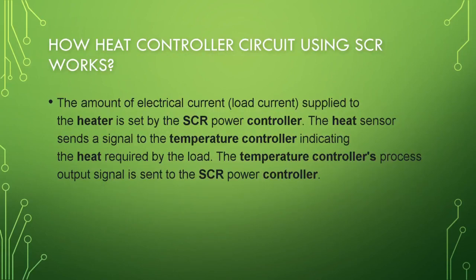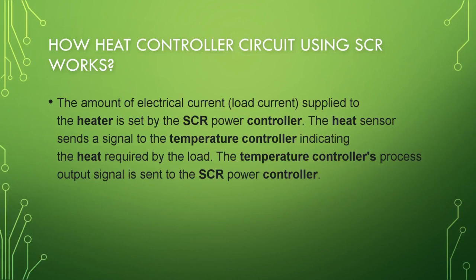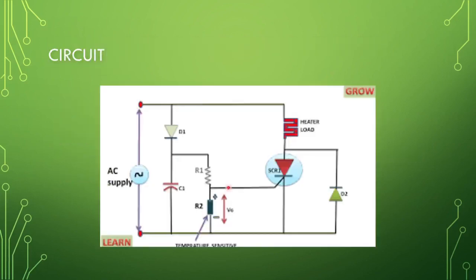Now, how does a heat controller circuit using SCR actually work? The amount of electrical load current supplied to the heater is set by the silicon controlled rectifier power controller. The heat sensor sends a signal to the temperature controller indicating the heat required by the load. The temperature controller's output signal is then sent to the silicon controlled rectifier controller.